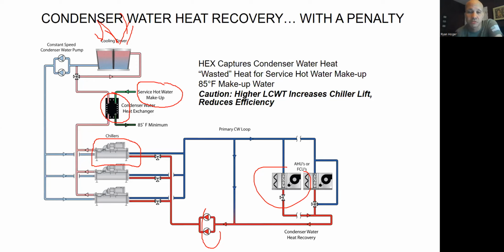I'm going to throw those BTUs into my space. However, when you do this, the chiller operates with significantly less efficiency than if you just dumped it into the sky. The reason is that this service makeup water is coming in much cooler than this water would have been, like in the summertime, right? In the summertime, my chiller is expecting to get 85-degree water delivered to it by the cooling towers. And that's what they're all designed and selected for and all that great stuff.